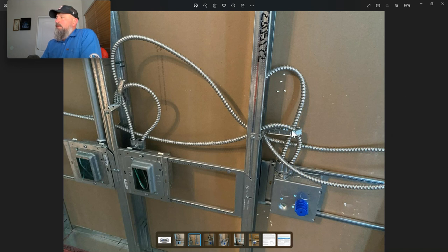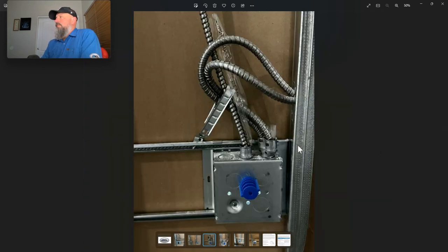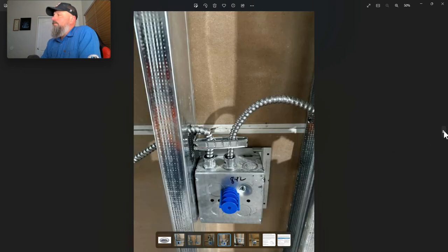Again, right here. Just over bending to try to get into that first punch out. Going over here, and we just got too much pressure on there. Again, just trying to get into that first punch out. Just over bending. Nice service loop. We'll go right in there and relieve all that pressure. It's pulling here, it's pulling here. It's just way, way over the bending radius. And this is just unnecessary. I mean, we should be cutting all of these off. We shouldn't have any of this sticking out. So let's go to the next one.